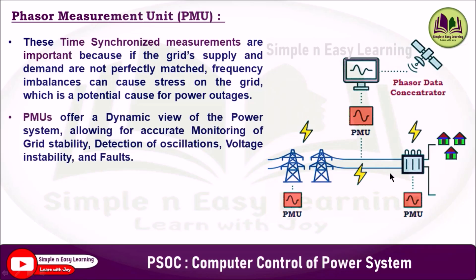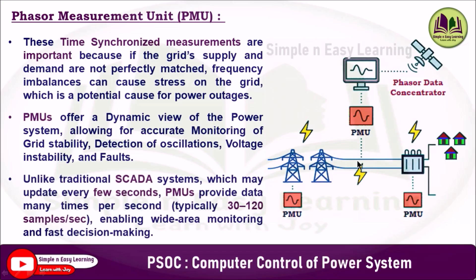Phasor measurement units offer a dynamic view of the power system, allowing for accurate monitoring of grid stability, detection of oscillations, voltage instability, and faults. Unlike traditional SCADA systems which may update every few seconds, phasor measurement units provide data many times per second — typically 30 to 120 samples per second — enabling wide-area monitoring and fast decision making.